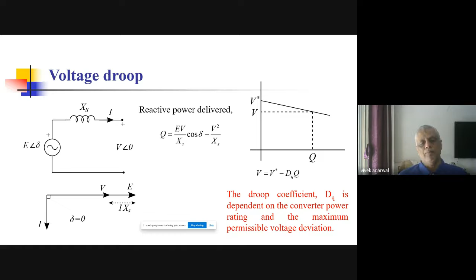You can see the voltage droop here. As the reactive power Q demand is increasing, the voltage is decreasing. So the generators have to be told that, all right, here is the information about the reactive power being demanded by the system, and this is the voltage that we are getting. So this is the reactive power that you must feed to get a specific voltage output. That automatically happens in the conventional system, but in your microgrid system, if we incorporate this kind of characteristic, then we'll be able to instill or incorporate stability in these systems as well.